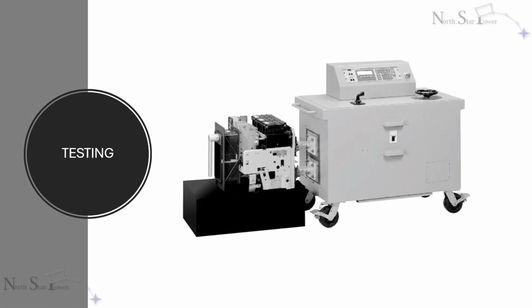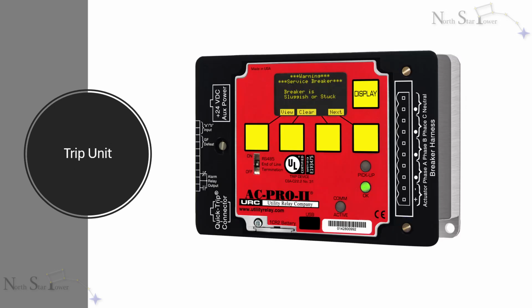Each type of equipment in a power system demands a specific set of tests. Let's focus on circuit breakers, beginning with low voltage. To verify they'll perform correctly during fault conditions, we begin with primary injection testing. The brain of a low voltage breaker is the trip unit, an internal control system wired into sensors that monitor electrical current. It's programmable and reacts to different types of faults.